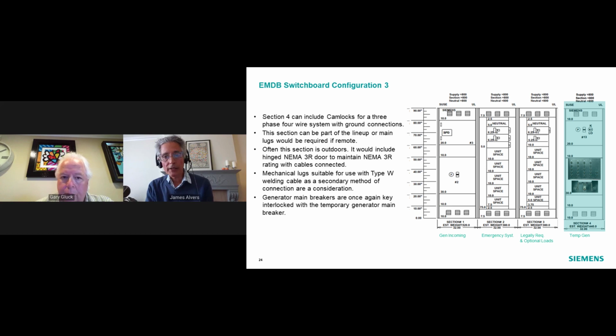Another option for that last section is to have cam lock connections. So this particular section can be just part of the overall switchboard, or it can be mounted remote, in which case you'd need some lugs on the main switchboard. Often it's outside, so it's NEMA 3R.